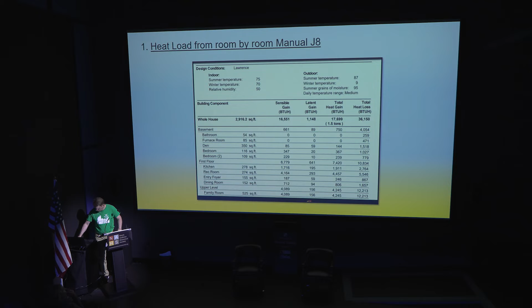So when analyzing if an air to water heat pump would work to reuse our existing water baseboards, we need to know, well, at the air to water heat pump output temperature, is enough heat going to be distributed to each of these rooms? And the air to water heat pump that was available at the time had a maximum output temperature of 130 Fahrenheit water compared to the natural gas boiler it was replacing, which is 180. So it's not nearly as hot in terms of the water that's being output.